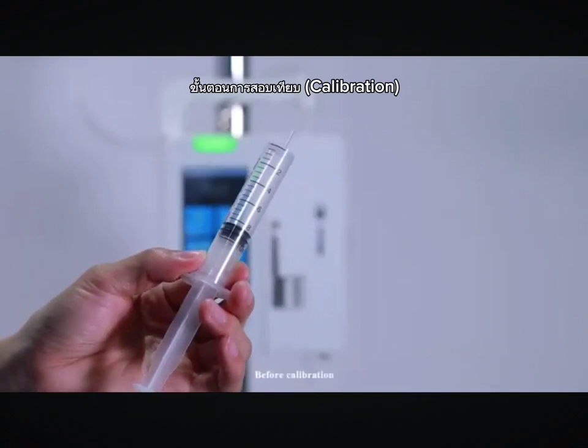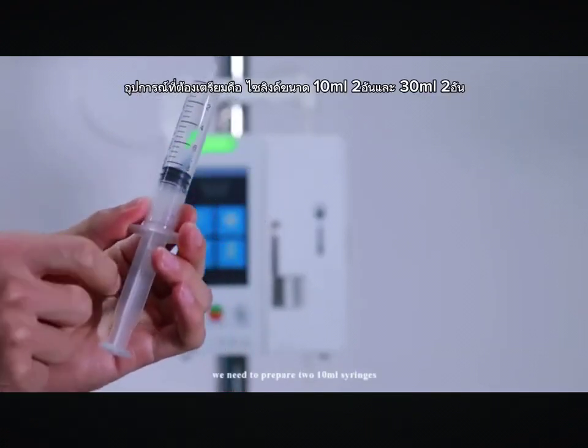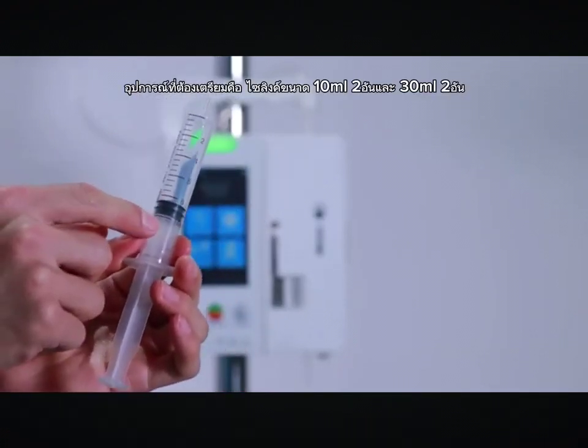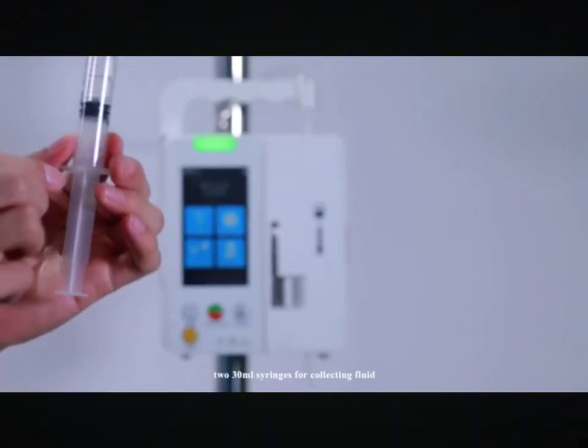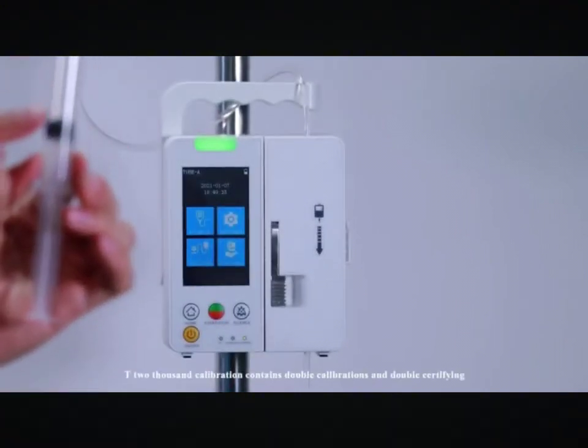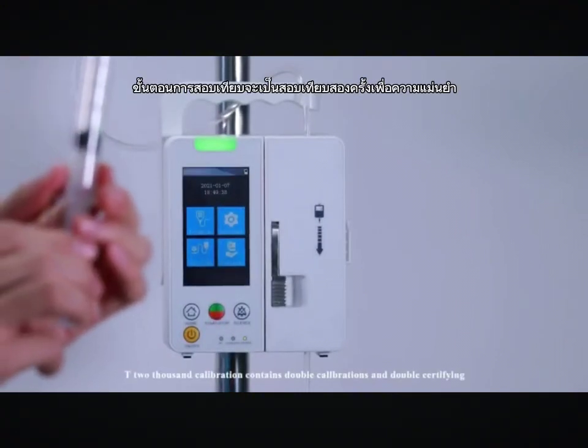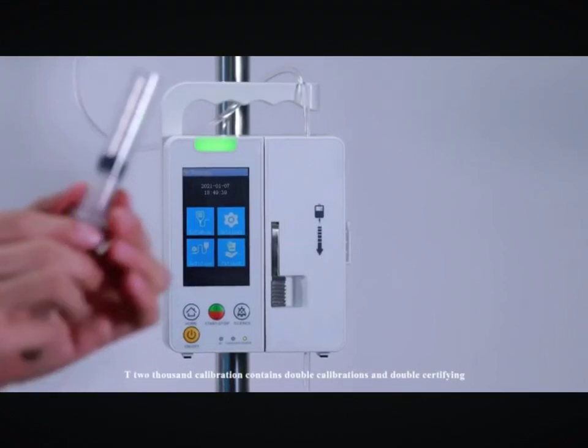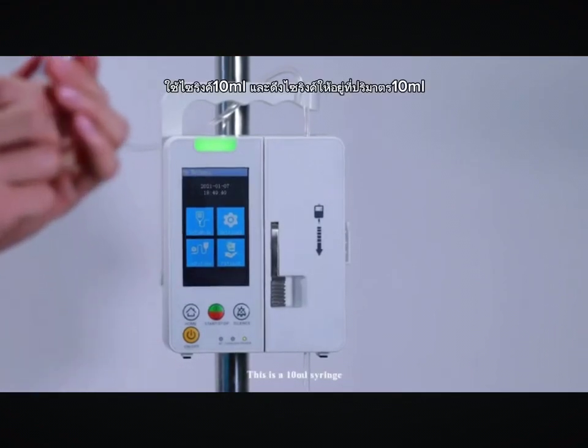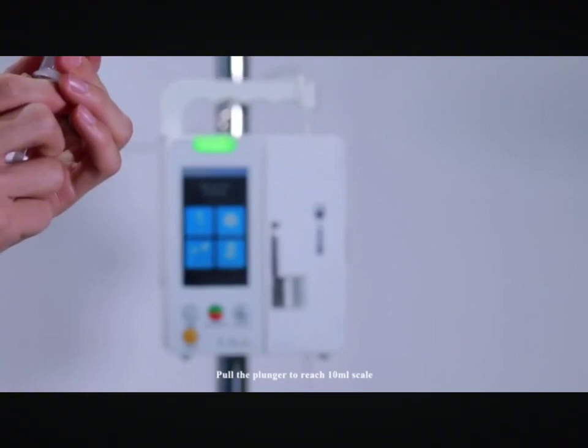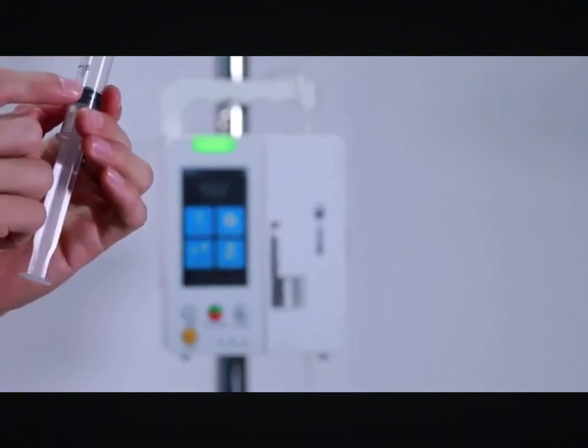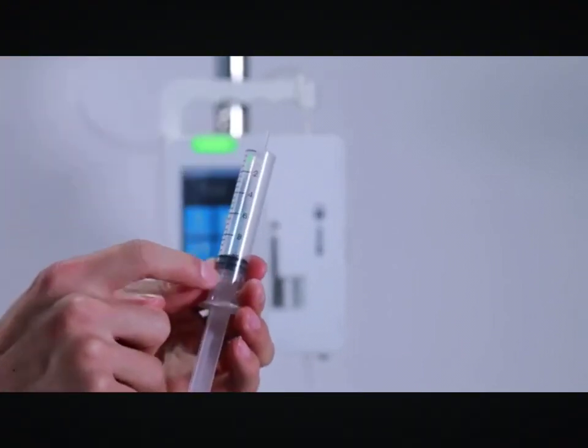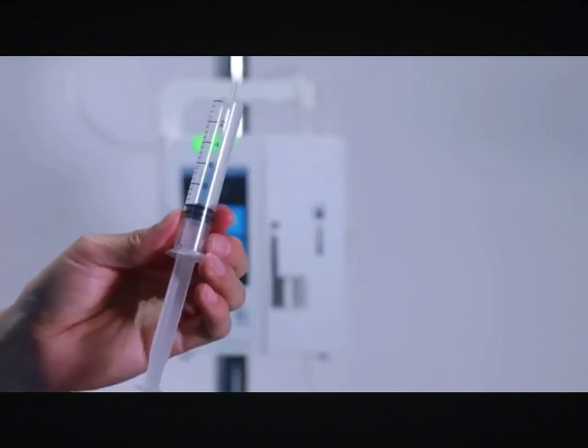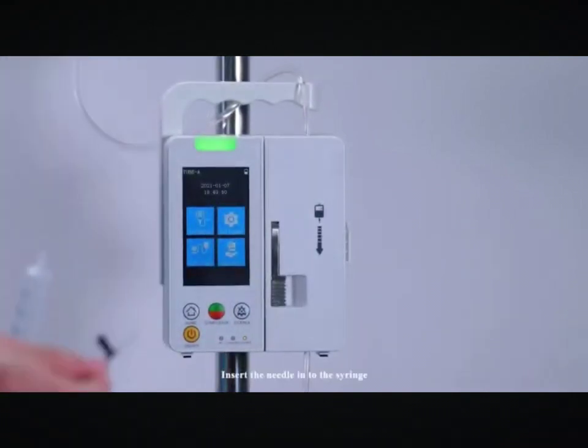Calibration. Before calibration, we need to prepare two 10 ml syringes and two 30 ml syringes for collecting fluid. T2000 calibration contains double calibrations and double certifying. This is a 10 ml syringe. Pull the plunger to reach the 10 ml scale. Insert the needle into the syringe.